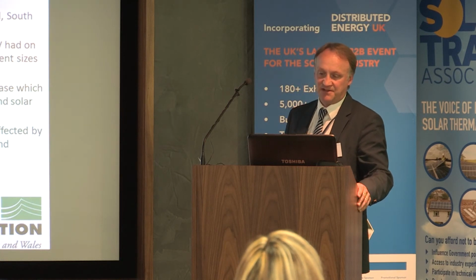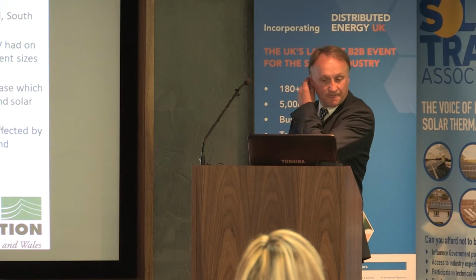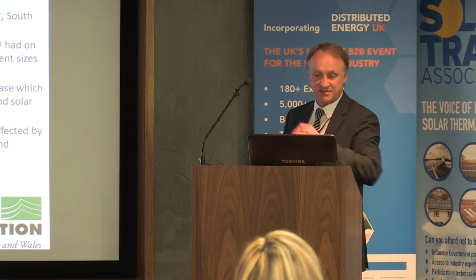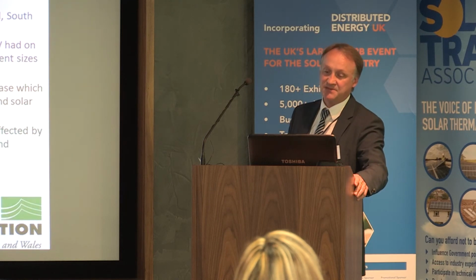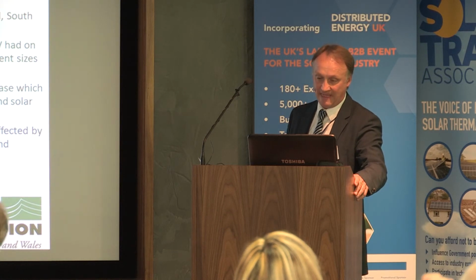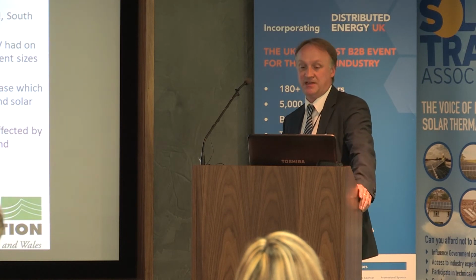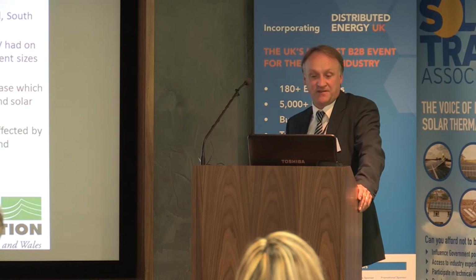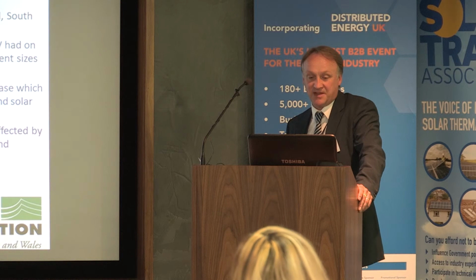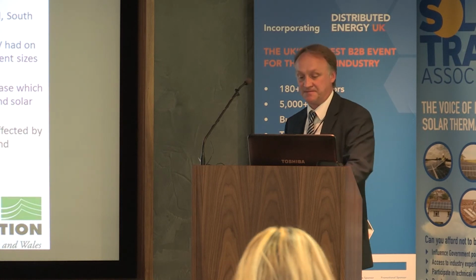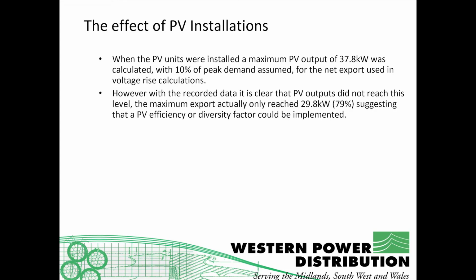Monitoring was installed mid-feeder and at feeder end for each phase, and was complemented by extra data on PV output, tap change data and solar irradiance. Now, the key learning from this project is that the voltage is not significantly affected by the LV main impedance or by the panels, leading us to recommend revisiting the LV planning assumptions. When the PV units were installed, a maximum PV output of 37.8 kilowatts was calculated, with 10% of peak demand assumed.